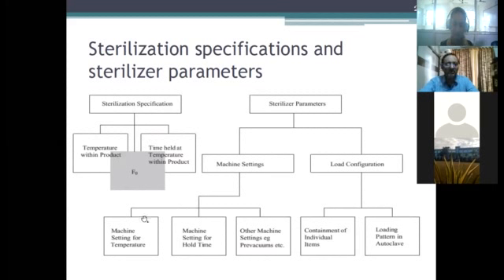So that is about a chart which is showing you the specifications, machine settings, and load configuration, which means the loading pattern in the autoclave. Let me stand over here. Loading pattern means if you do not load your products properly inside the autoclave, then also there is a chance of failure. Though the parameters of temperature and pressure will be correct on the chart and the dial, the product will fail because it was not put inside the autoclave properly as required. So these are things which have to be taken care of: temperature setting, time setting, pre-vacuum and other settings, containment of individual items, and loading pattern in the autoclave. These are things which have to be taken care of.